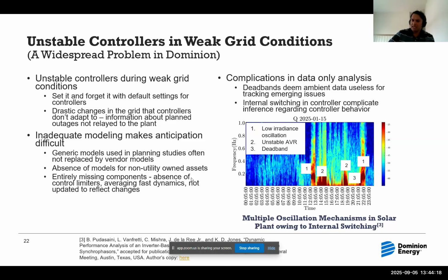One example: on the bottom right I plotted a spectrogram of reactive power output of a particular solar plant. Wherever you see these bright red regions is where there's an oscillation, but the mechanism behind the oscillation keeps changing. In early periods it's trying to do power factor control, so there's an oscillation resulting from that, but then it stops doing power factor control in between, so you don't see any oscillations.